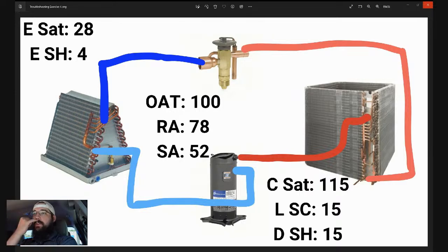To update your results at that point, I didn't have a different slide prepared for that, but I'll write them down and make sure I keep track. So we bump it to high speed fan. We start pushing 30 on our SAT. We get a superheat of 5. Our return stays the same, but our supply goes up to 54, we'll say. And the discharge superheat and the liquid line subcooling remain the same. So all we really changed was we bumped up saturation a little. Our superheat came up a little, but our supply air also came up a little, but nothing else was really affected in that process.